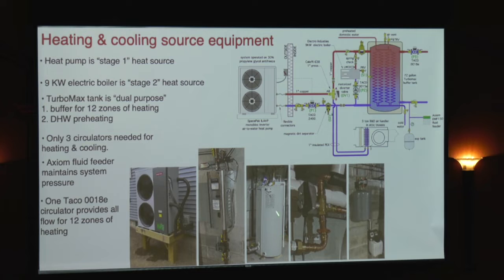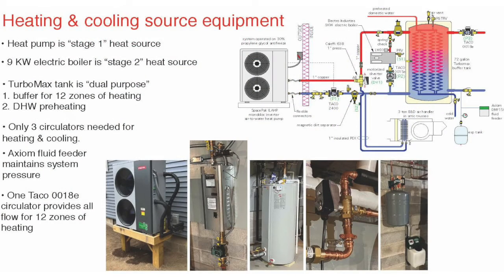Here's the buffer tank. This is the valve. This is a 1-inch motorized 3-way ball valve, and it's got a 24-volt actuator. Power goes to one lead, turns it all the way to one direction. You power another lead, it goes all the way in the other direction. I'd have to look it up, but I think it's 30 seconds, 60 seconds, something like that. It's not an instant move, so it powers over.